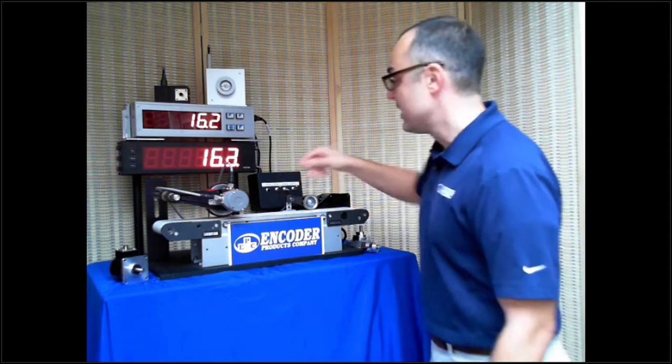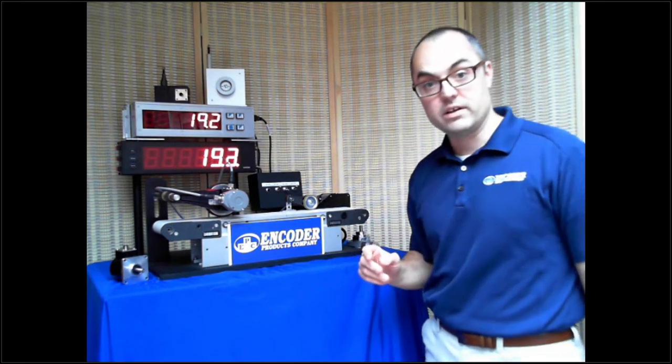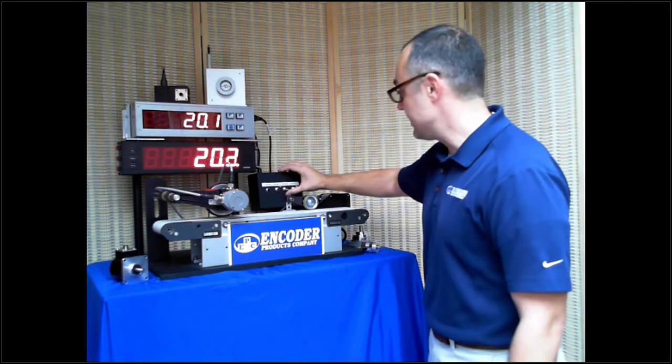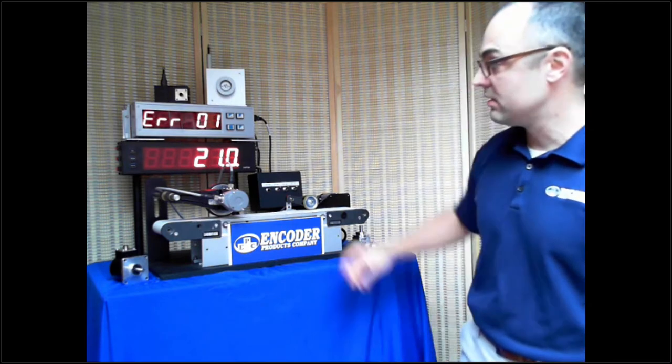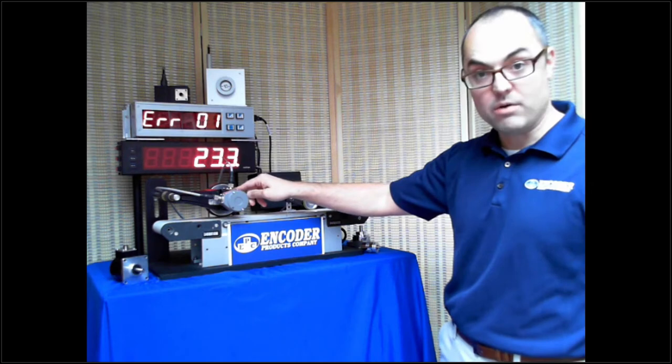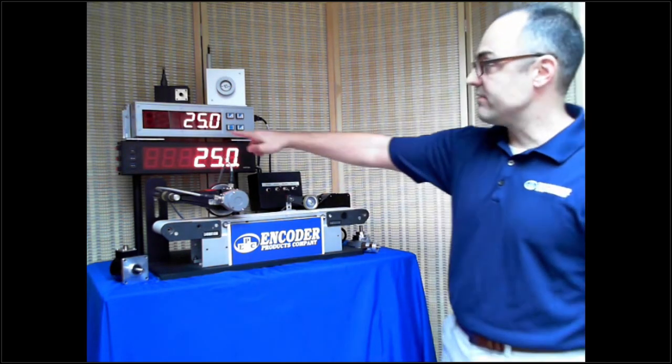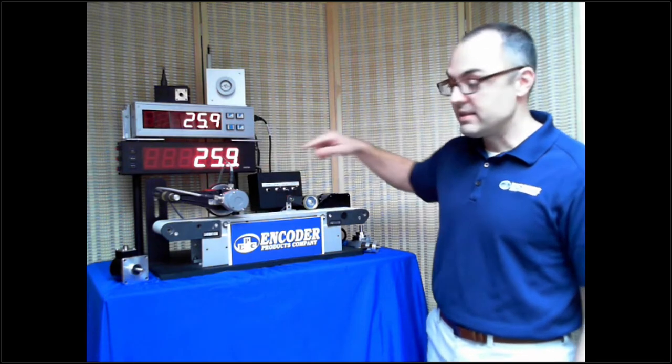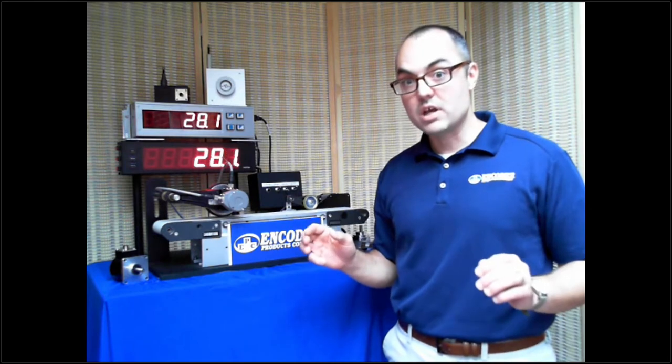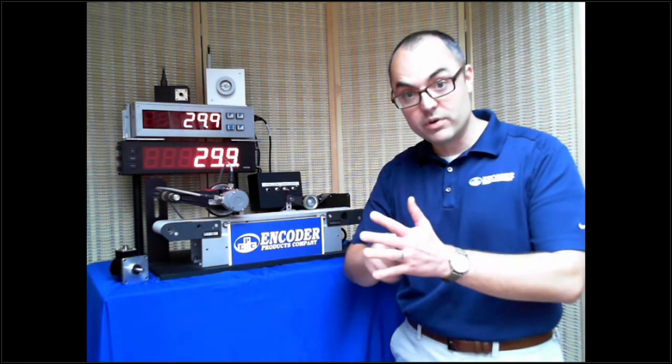Yep, and all three methods can do that, whether you're using gears or batteries or energy harvesting. So why do we care? Well, this is why we care. If I turn this encoder on, so now that it's moving our position is changing, and all of a sudden we're at the factory and we have a power loss, and I turn off this absolute power but I'm still moving. Now I have motion while I'm not powered. And I turn this back on - we have not lost our position.